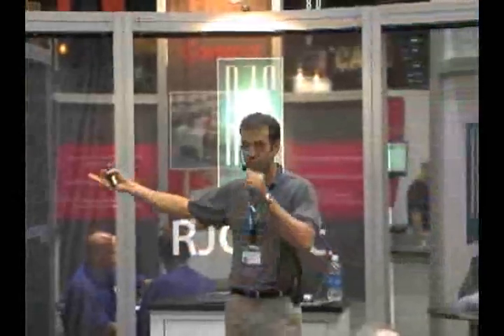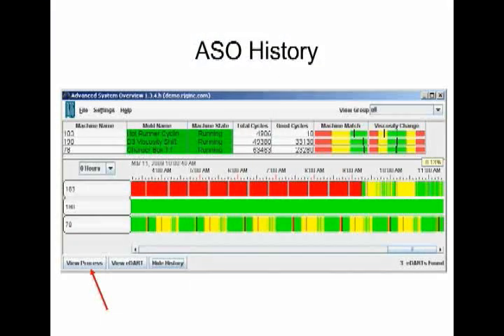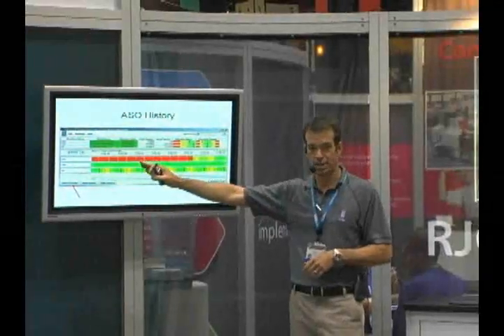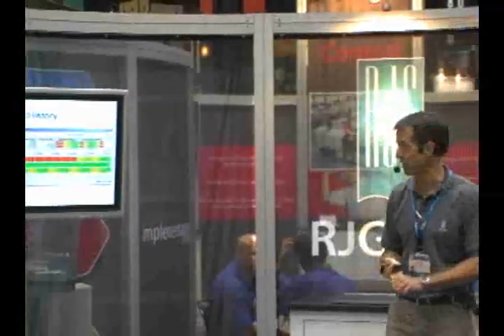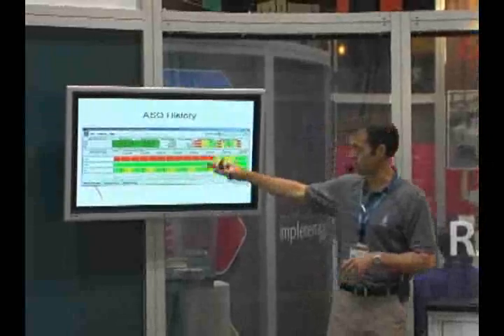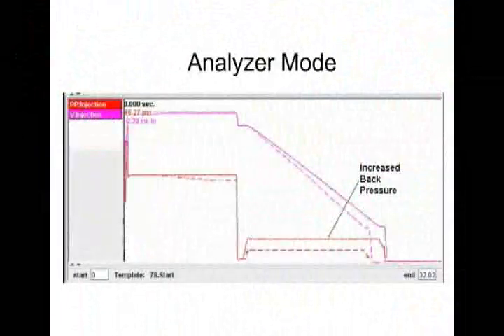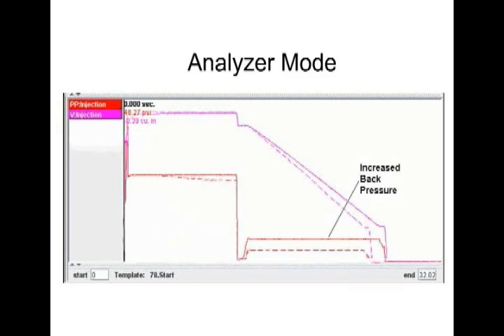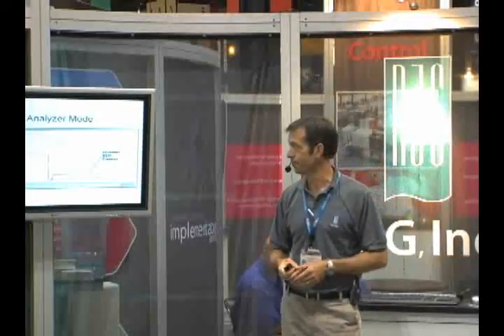So you come in at 7 in the morning, made this tour, you've looked at the PC right on your desk, understand there were some issues, and you want to know how long those issues have been going on. Well, the system will track that variation for the last 24 hours, and you can see if the problem's been occurring all night, if it's a random variation, that type of thing. And now I can focus on a specific machine, one specific problem. Now I can go down to the detail. But without ever having to go there, depending on the design of the personnel on your floor, it's a step-by-step approach to efficiently identify whether or not you're running to your validated process.